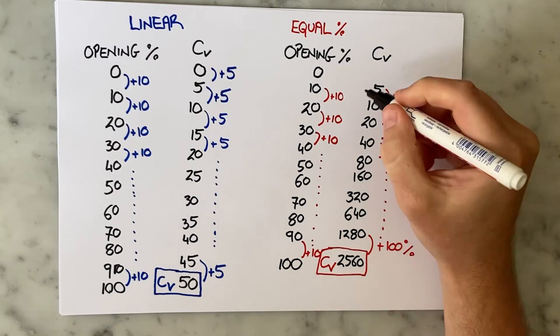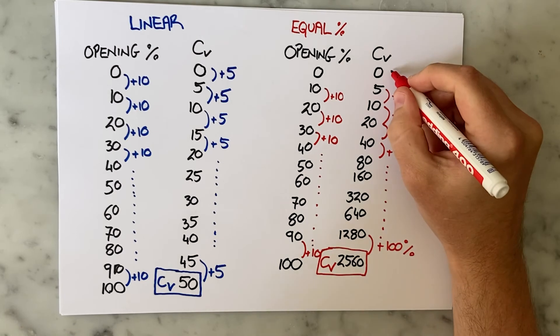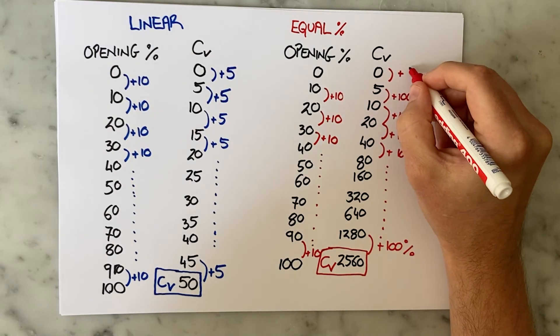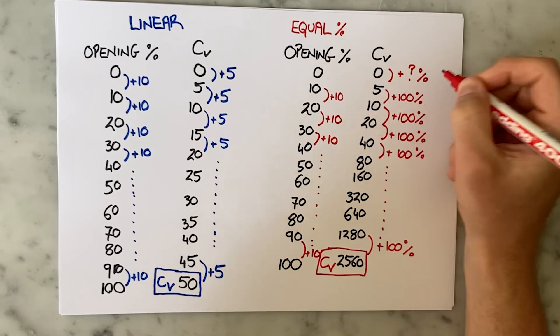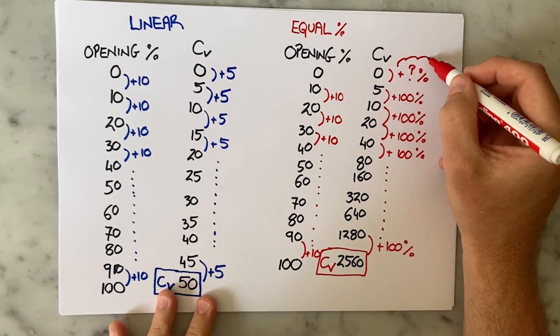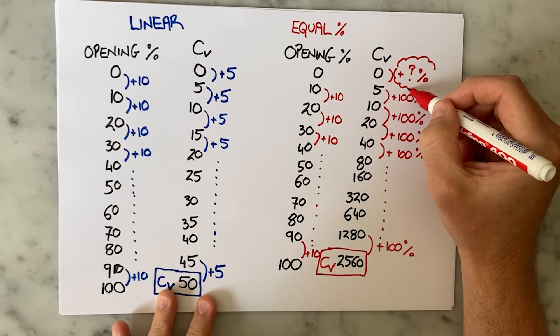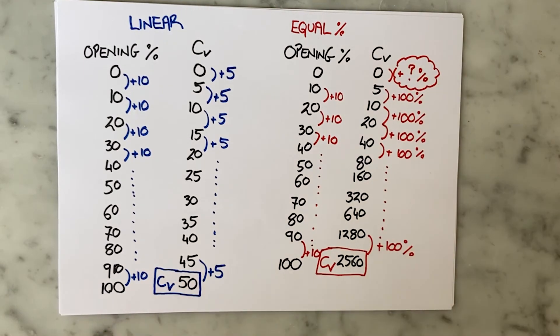For the linear valve all I had to do was add 5. But what do I do for the equal percentage valve? If the flow rate is 0 and I say OK I'm opening up to 10%, I need the flow to increase by 100% to carry on with the pattern. But 100% of 0 is still 0, so that doesn't help. That is why I couldn't start at 0%.